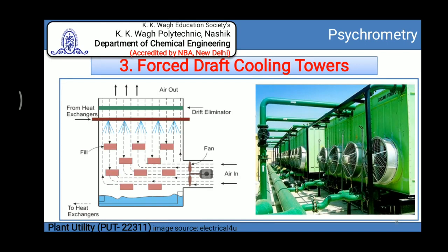The forced draft cooling tower is a type of mechanical draft tower because they use fans to move air inside the cooling tower. Forced draft towers use fans at the bottom of the tower in order to push the air inside the cooling tower. The forced mechanism makes it relatively more efficient than the natural draft towers. If the fans are not big enough, then it may cause the motion of the air to become non-uniform while it passes through the fill material.